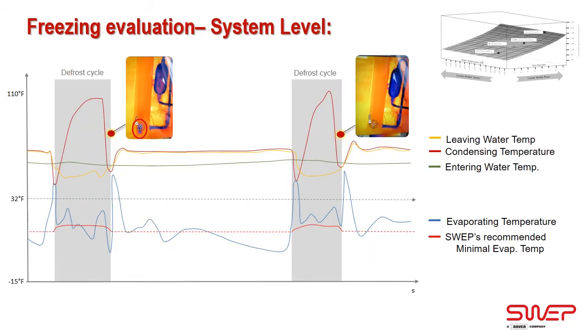So far, we have been discussing how we evaluate and define the freezing boundary of a specific heat exchanger, and also how we can compare BPHE designs between them. But for you, I think what is the most interesting is to understand how you can use it in your system. For that, I would like to share with you an example from a cooperation with one of our European heat pump customers. On this slide, we will focus on the gray area, which is when they run the defrost cycle. During other periods of time, the brazed plate heat exchanger is used as a condenser, so there is no risk of freezing. What we did was to evaluate the possibility to use a polynomial function extracted from our 3D graph as a freeze protection. For that, we compared it with another method, which is what we call visual freeze detection.